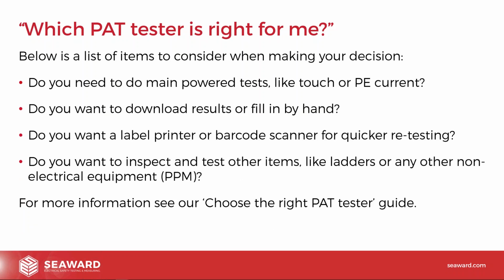Do you need to do the mains powered tests like the touch current and protective conductor current that we talked about? Our battery powered testers like the 50 and the 100 won't do those. They'll do alternative leakage tests, but they won't do the mains powered tests. Do you want to download results or fill in by hand? Again, that's the difference between the prime test range of testers, the manual testers, and going up to the Apollos, the downloading testers.